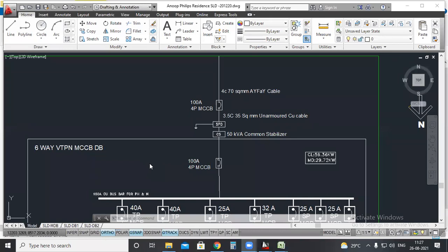30 kW, yeah, 30 kW. How do you assume the 30 kW load? What all equipment will be turned on during peak hours? Kitchen and AC working. Okay, kitchen. Even if you take the kitchen, only one or two pieces of equipment will be turned on at a time.